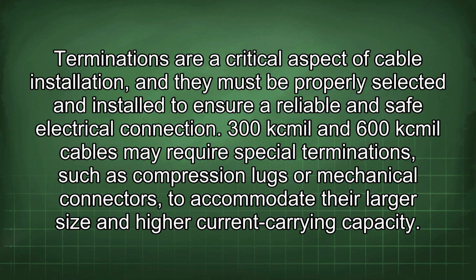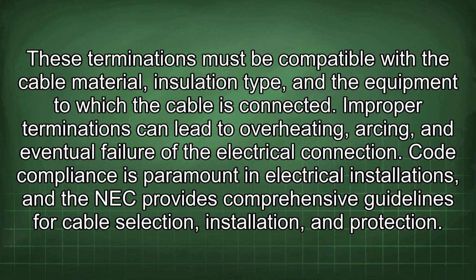Terminations are a critical aspect of cable installation, and they must be properly selected and installed to ensure a reliable and safe electrical connection. 300kcmil and 600kcmil cables may require special terminations, such as compression lugs or mechanical connectors, to accommodate their larger size and higher current carrying capacity. These terminations must be compatible with the cable material, insulation type, and the equipment to which the cable is connected. Improper terminations can lead to overheating, arcing, and eventual failure of the electrical connection.